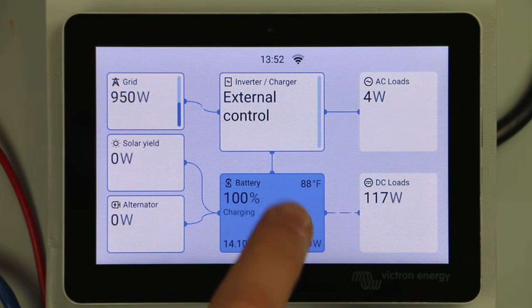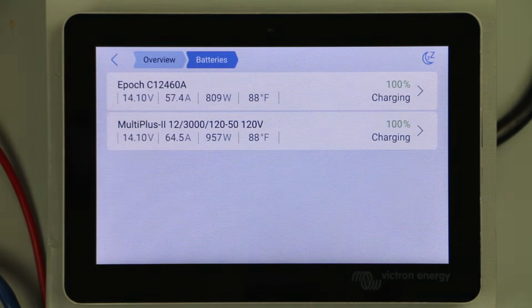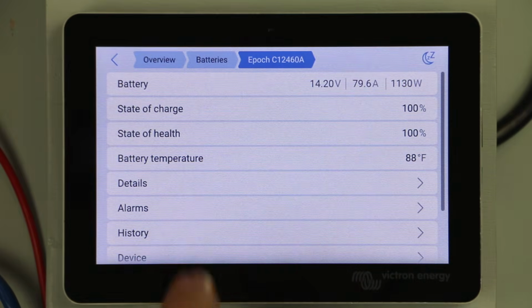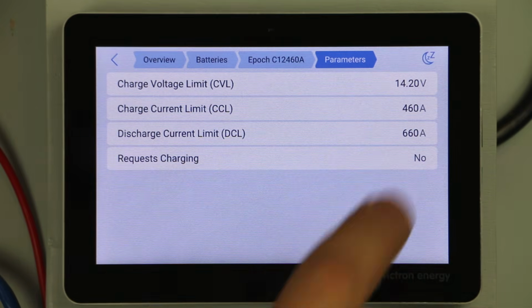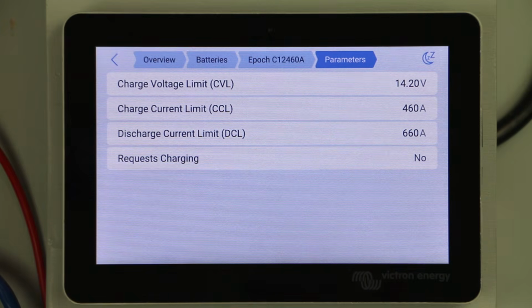If we look at our battery parameters, it'll still say 14.2 volts on our charge limit. But in 30 minutes, that's going to drop down to 13.5 volts for our float charge, and it'll stay at 13.5 as long as your charger is plugged in, whether that's days or a week or two weeks. It's going to stay at that float voltage and power any DC and AC loads that turn on.